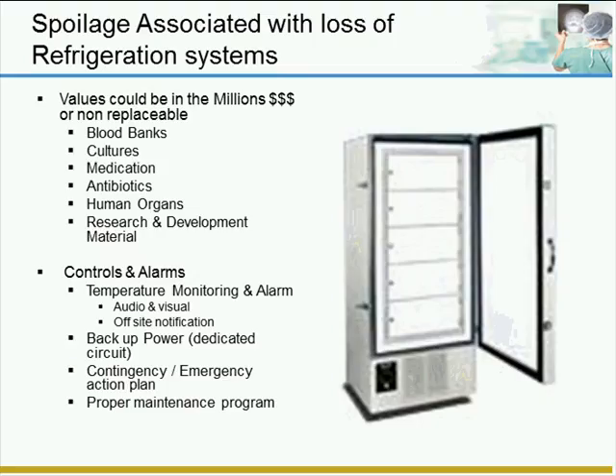Temperature alarms should be on all units, visual and audible alarms. They should be connected to an off-site notification system, which will prompt someone off-site in the event of a high or low alarm and/or a power loss at the facility. Emergency action plans should be maintained. The action plans could include redundant systems, a spare freezer on site, for example. The freezer should be connected to an emergency generator. If you do lose power, the generator will supply the electricity to the unit. And in some cases, you'll have a nitrogen system, which will also be used as coolant.